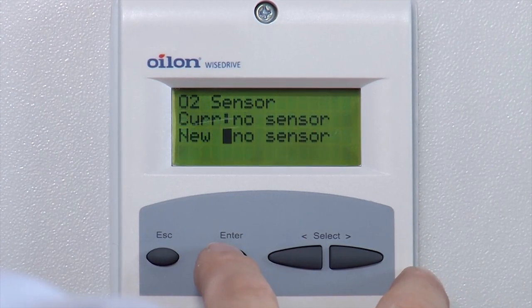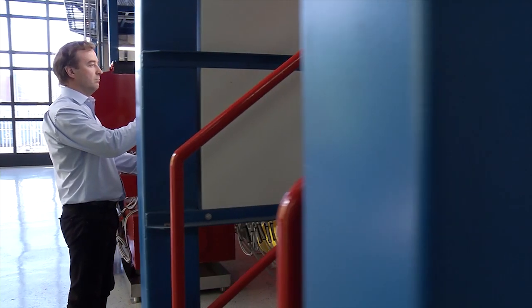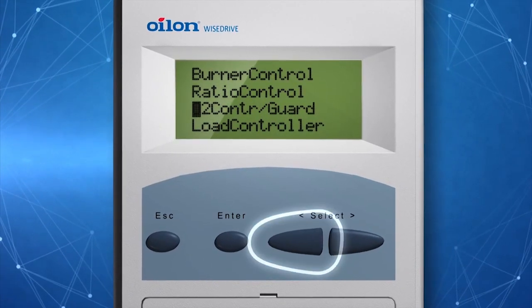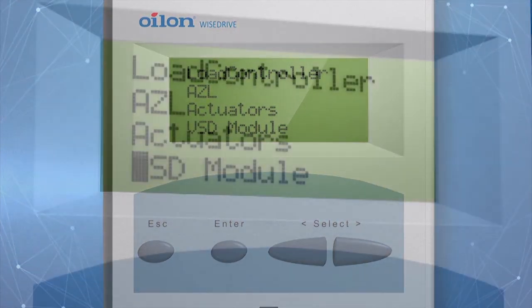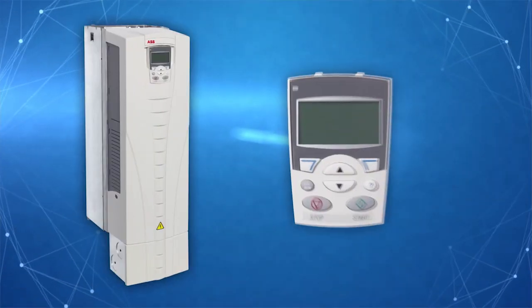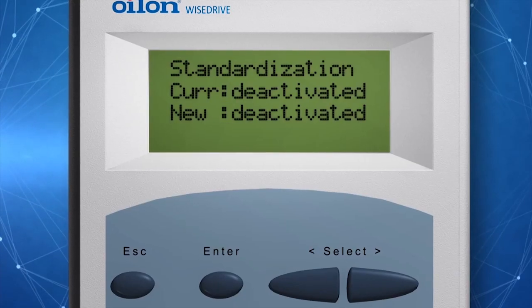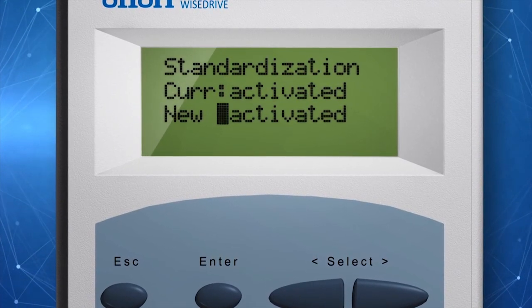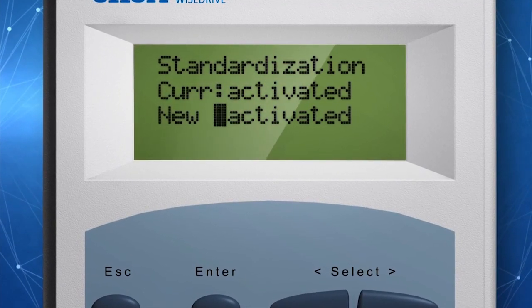Before the first start-up, you will also need to set the frequency converter parameters for the fan motor control. After activating the oxygen module, standardize the frequency converter. You can do this in the submenu VSD module. The frequency converter parameters must be set for the fan motor control — refer to the manufacturer's manual. The settings you need to change are the acceleration and deceleration time and maximum and minimum frequencies. You can find detailed instructions in the burner manual.